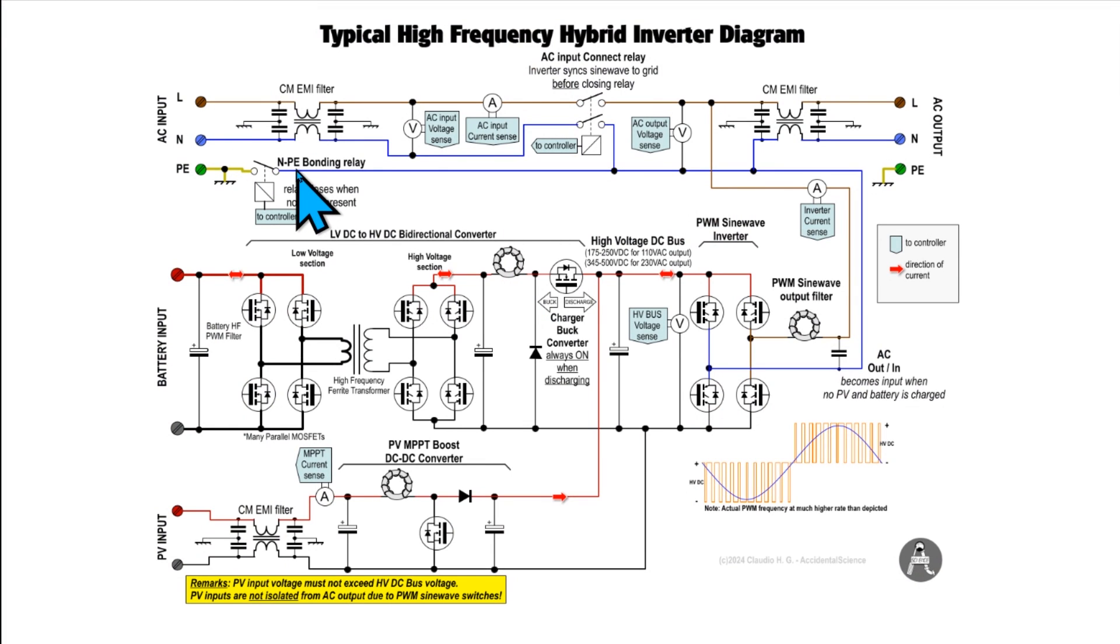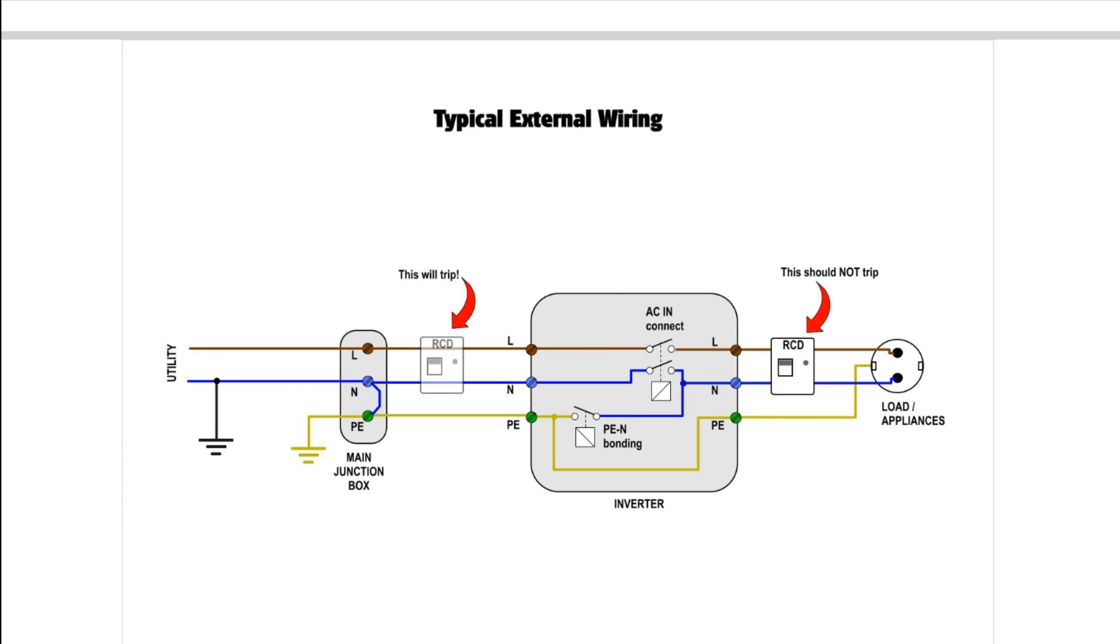An important critical point is the neutral protective earth bonding relay. This is important because when we open this switch, this relay, and we detach the inverter from the grid, the neutral now becomes floating in respect to the protective earth. So it is necessary to close this contact to restore this connection, this bond with the ground.